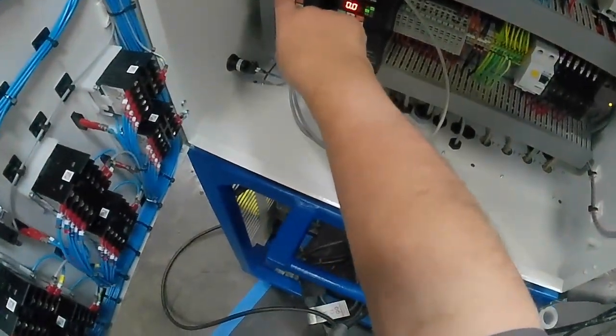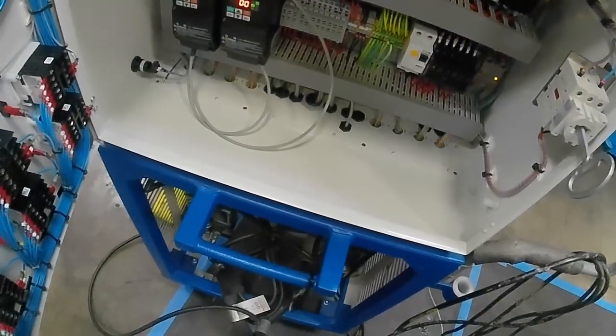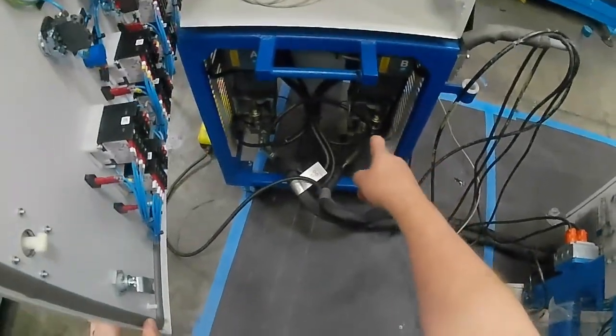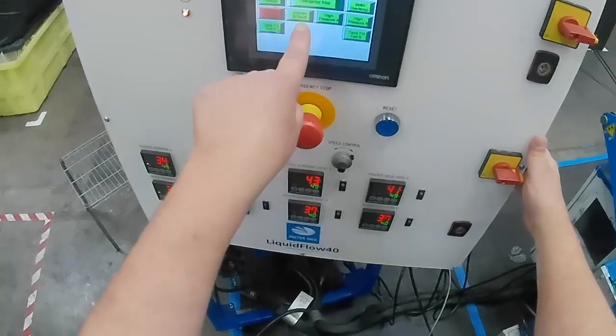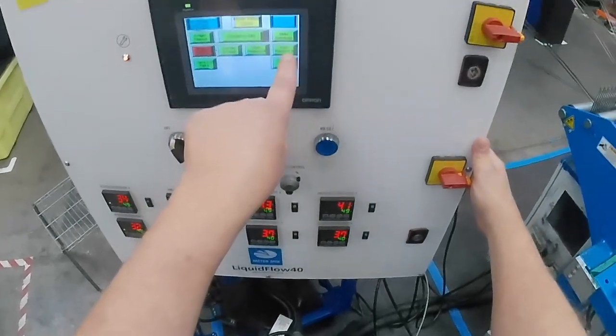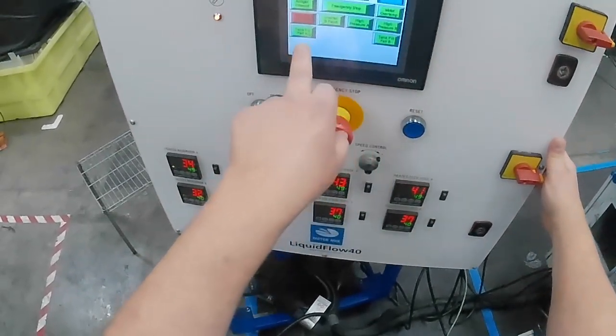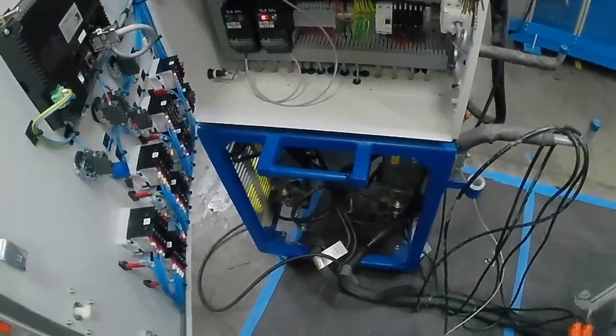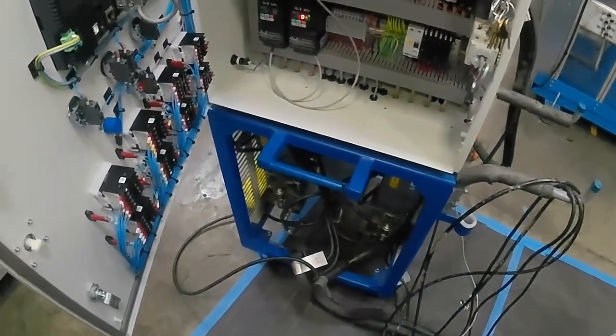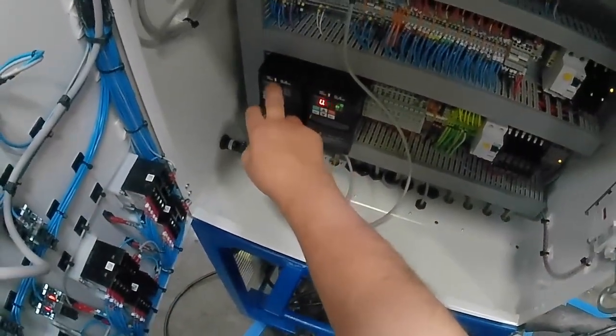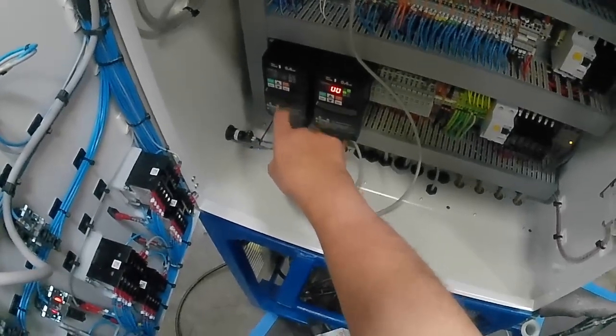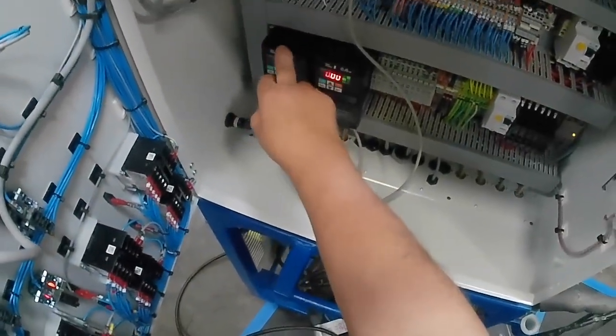And it is a single phase inverter. One is on, which must be B, and A is off. B inverter is on. High pressure A, high pressure B. Tank fill A, tank fill B, but he is off. Oh crap. All right, let me get a voltage reading off this guy and see if we have voltage coming in to the supply side of this inverter.